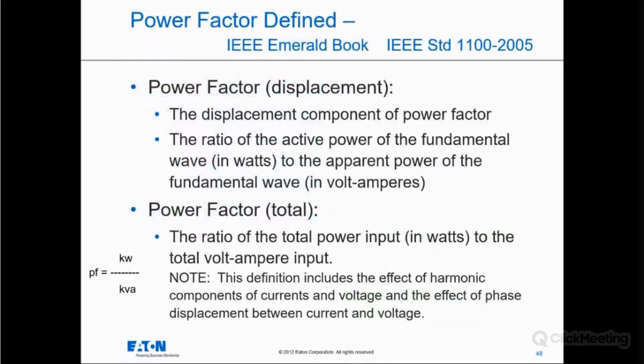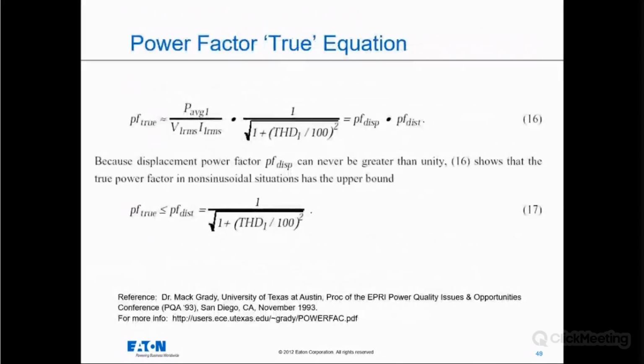So up to this point, we've been talking about power factor correction and what would be referred to as historic power factor or displacement power factor. That poor power factor coming from inductive loads in your facility like motors. But if you get a meter and you look at total power factor, that actually is accounting for two things. Historic or displacement power factor coming from inductive loads, but also a distortion element coming from nonlinear loads distorting the waveform. So if you look at the actual formula here, true power factor comes from displacement power factor times distortion power factor.